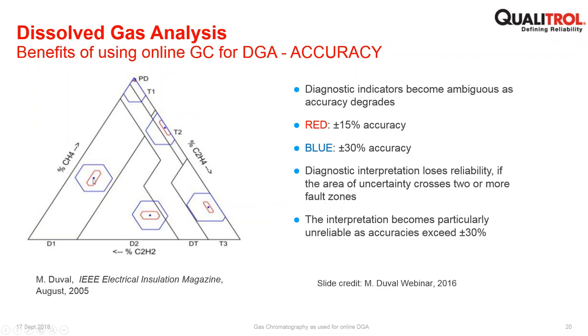What's shown in the blue dot is the actual coordinate point. But for an online GC system, at plus or minus 5%, you're going to be very, very close to that central coordinate point, and therefore very, very precise in your diagnosis, which is ultimately the definition of what dissolved gas analysis is about.